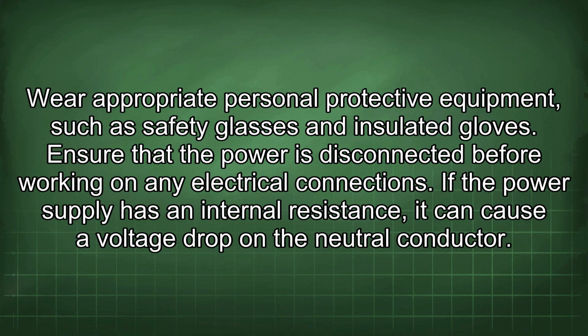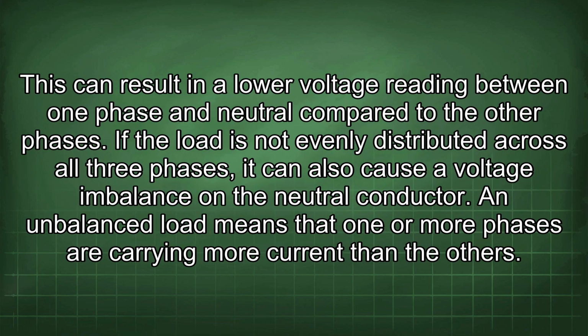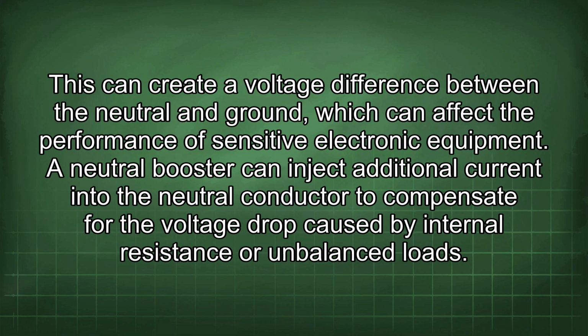If the power supply has an internal resistance, it can cause a voltage drop on the neutral conductor. This can result in a lower voltage reading between one phase and neutral compared to the other phases. If the load is not evenly distributed across all 3 phases, it can also cause a voltage imbalance on the neutral conductor. An unbalanced load means that one or more phases are carrying more current than the others. This can create a voltage difference between the neutral and ground, which can affect the performance of sensitive electronic equipment.